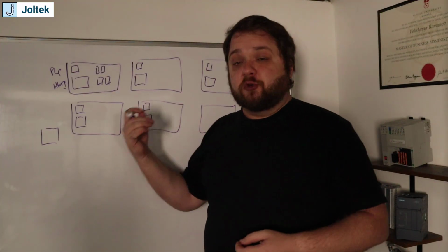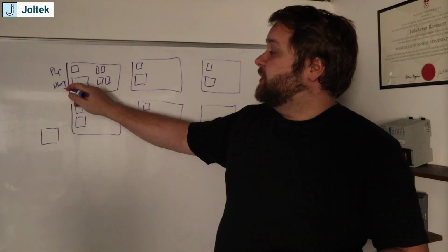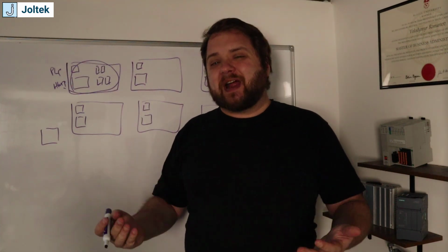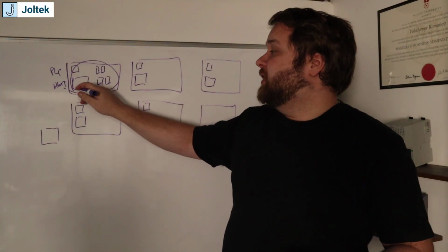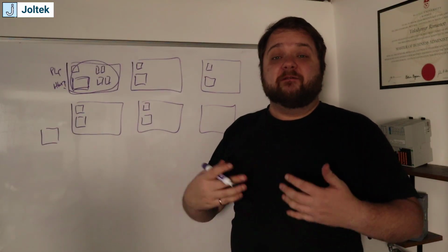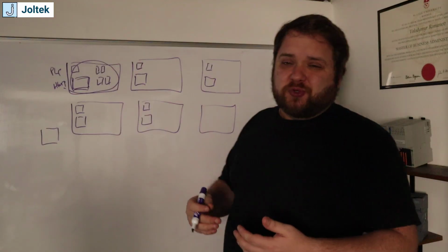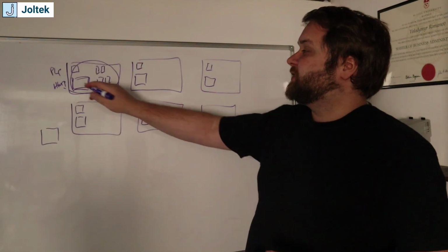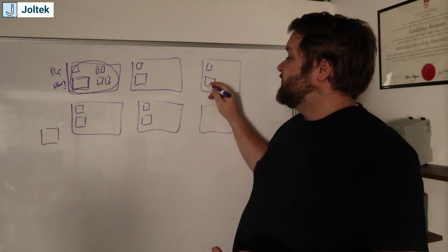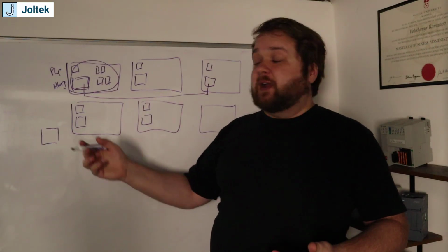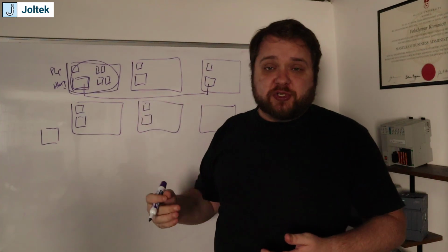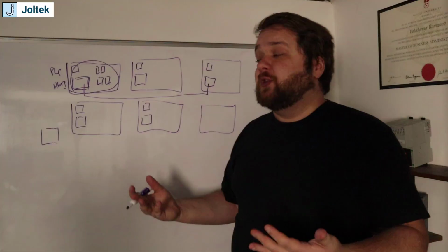Now, your HMI and your PLC are going to be basically the control system for a local area. It is to some extent impractical to allow, for example, the HMI on this machine to control a process that the operator has no visibility over. There are, of course, going to be exceptions to that rule. If, for example, this operator needs to see what the downstream machine is doing, it is possible to pass data from this HMI to this HMI for him to be able to have a signal that will consume the data between the two HMIs, but ultimately give a visual to that operator.